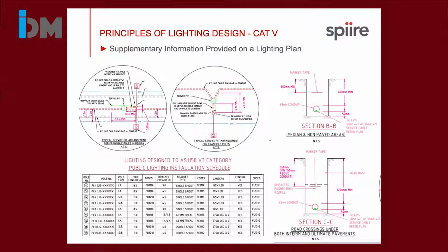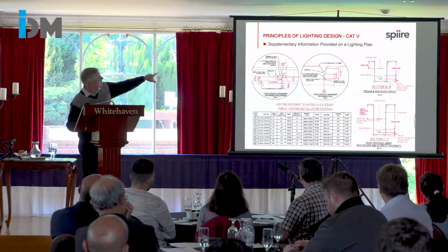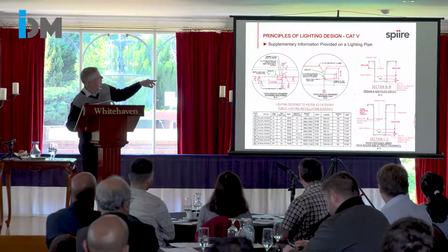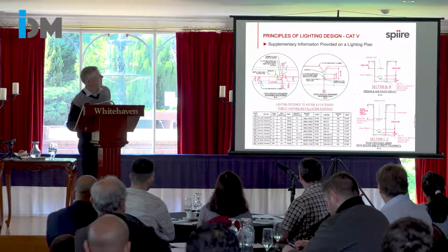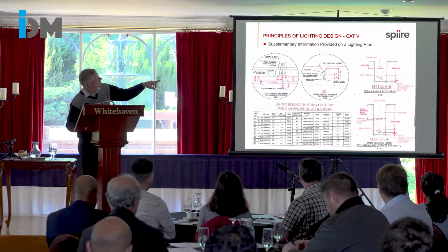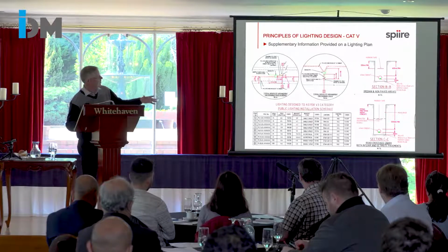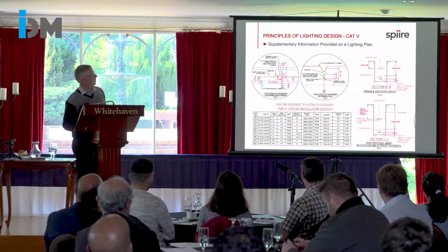Looking at plans that are submitted, you will typically see this sort of thing, which is your typical service arrangement. In this case here, we had guardrails in the median, and we also needed an offset from the guardrail, but also an offset from the electrical cabling within that median strip so that it can get past the pole, but not be too close to the footings of the guardrail, just in the event that the guardrail fails, you've got a truck go through it.